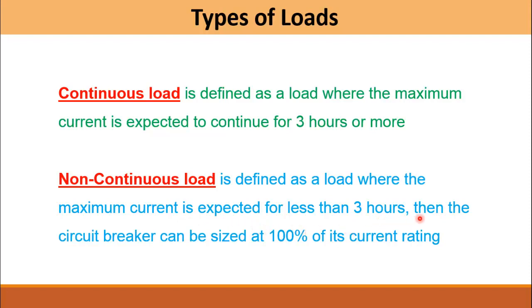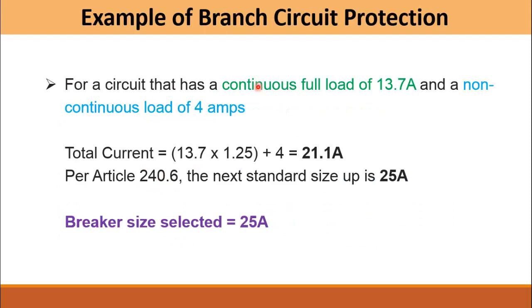Let's look at an example of branch circuit protection per NEC. We have a circuit supplying two load types: a continuous load of 13.7 amps and a non-continuous load of 4 amps. Applying the formula — 1.25 × 13.7 + 1.00 × 4 — the total comes out to 21.1 amps. Since 21.1 A is not a standard frame size, we move to the next standard size, which is 25 amps. Therefore, the proper circuit breaker rating for this combination of loads is 25 amps.